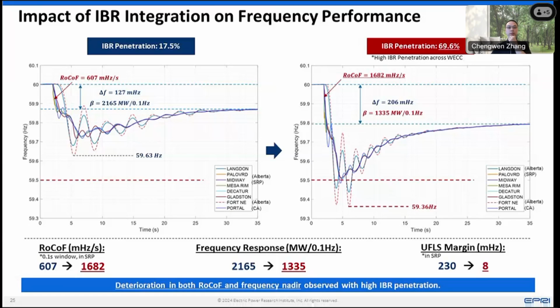That's almost 70%. Both the ROCOF, the rate of change of frequency—indicated by the insufficiency of inertia—and the frequency nadir deteriorated significantly. The ROCOF increased from 600 to almost 1700, and the frequency nadir got closer and closer to the under frequency load shedding point, to where it only had 8 millihertz of margin.